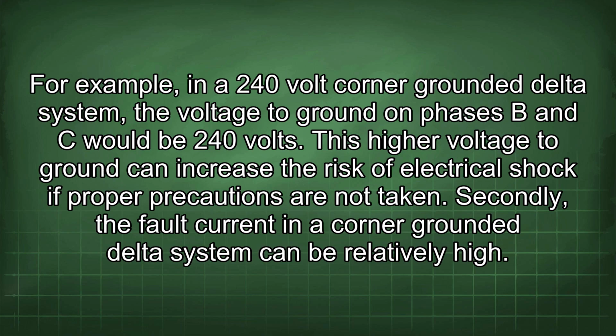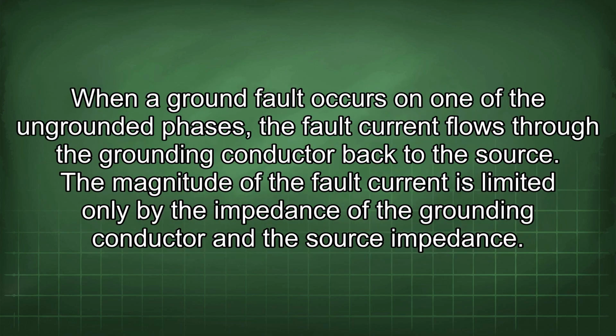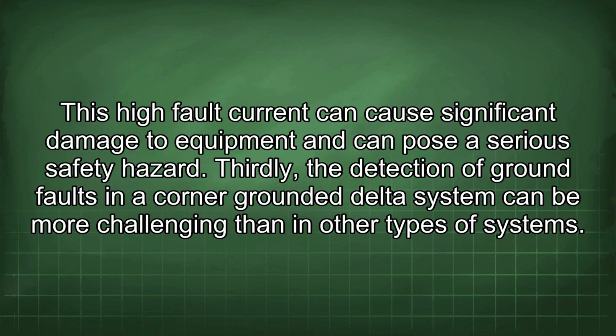Secondly, the fault current in a corner-grounded delta system can be relatively high. When a ground fault occurs on one of the ungrounded phases, the fault current flows through the grounding conductor back to the source. The magnitude of the fault current is limited only by the impedance of the grounding conductor and the source impedance. This high fault current can cause significant damage to equipment and can pose a serious safety hazard.